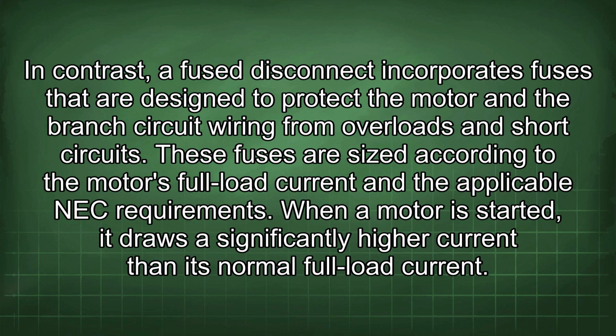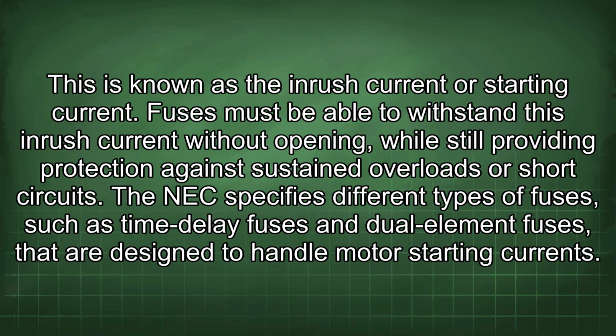When a motor is started, it draws a significantly higher current than its normal full load current. This is known as the inrush current or starting current. Fuses must be able to withstand this inrush current without opening, while still providing protection against sustained overloads or short circuits. The NEC specifies different types of fuses, such as time delay fuses and dual element fuses, that are designed to handle motor starting currents.